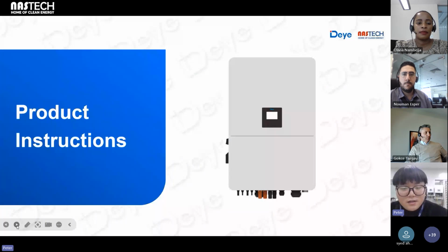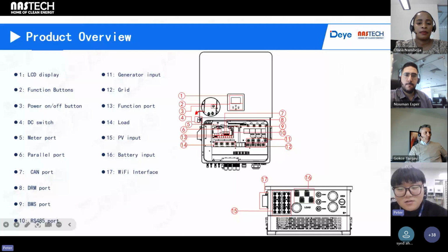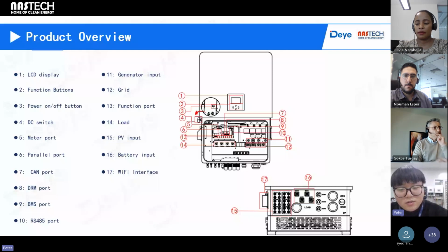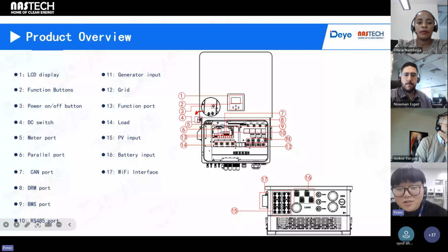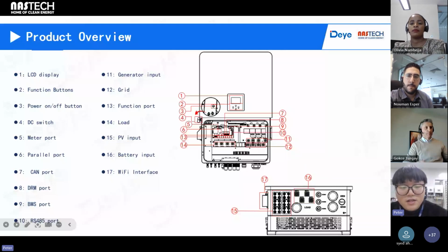And for the 80K inverter, the internal design is also similar to the 50K. So if the customers or the distributors have already sold the 50K, then they can learn how to use the 80K very fast because the design is very similar inside. Like the position for the load port and the grid port and the generator port is all the same, and the interfaces are all on the communication board. The position will remain the same as the 50K.